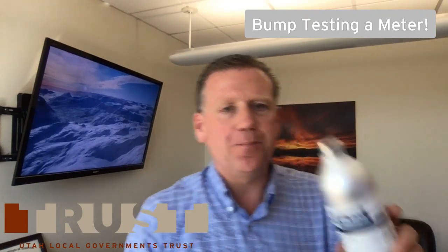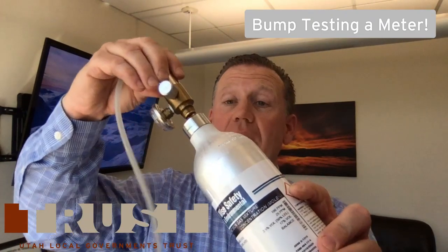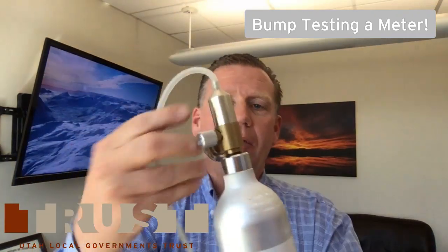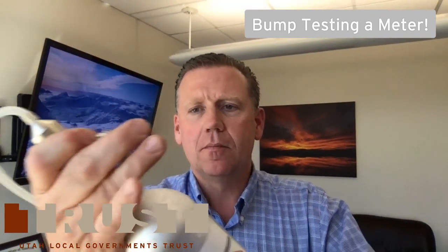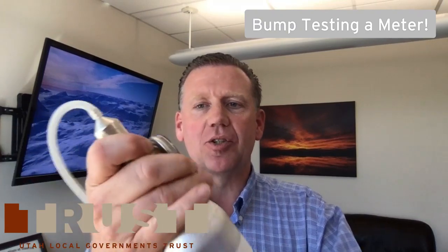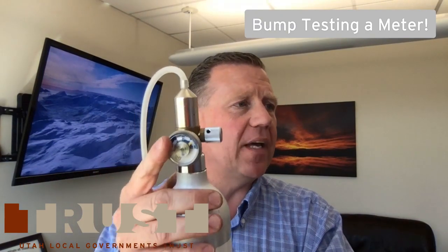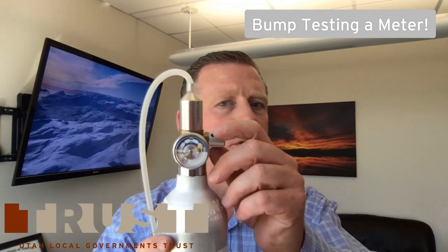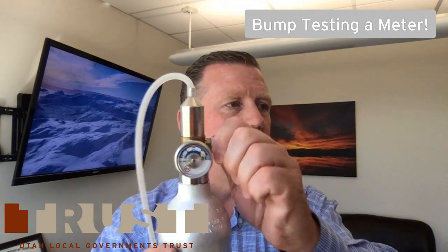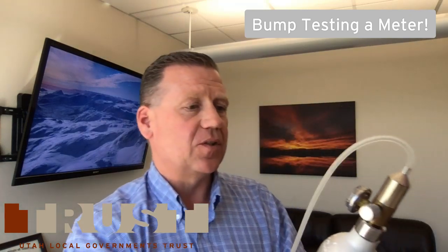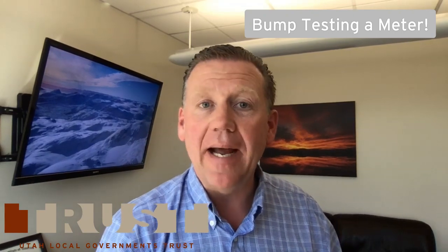We take this cylinder and we hook it onto a regulator. Pretty simple process. It just screws into place, screw it firmly in place. We have a gauge on there, and you'll notice as I turn this on, that needle goes up, and we're well over 700 pounds. So we absolutely have enough gas to be able to do a bump test. I've turned it off now because it stinks.